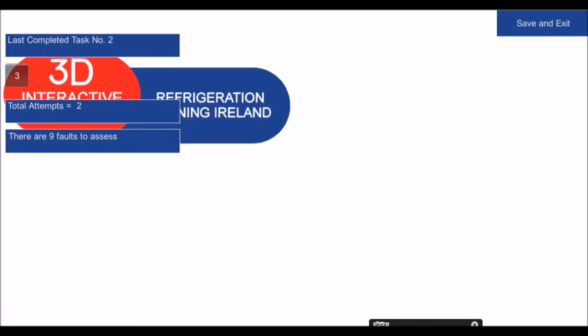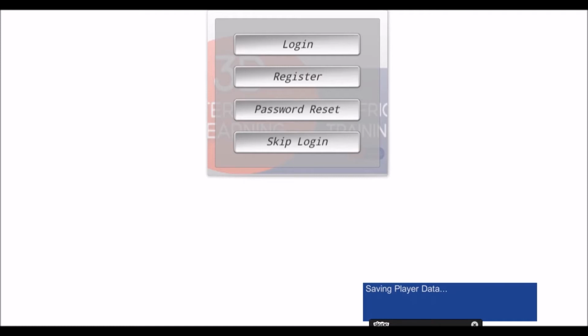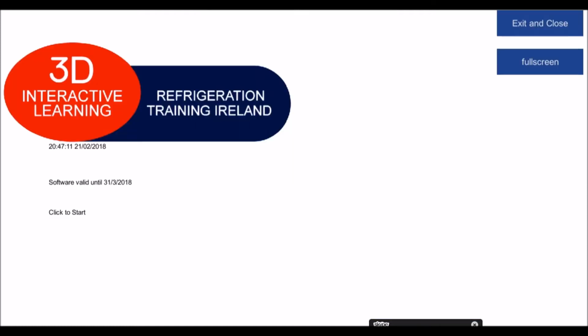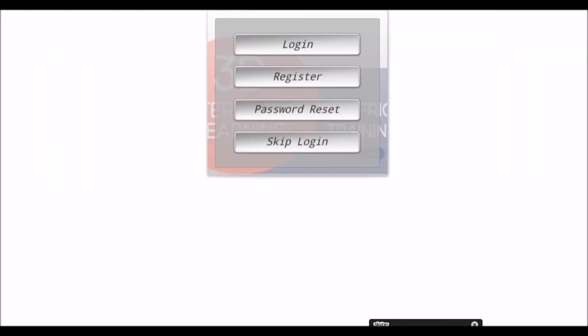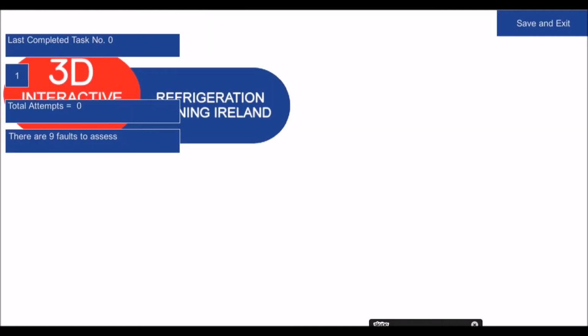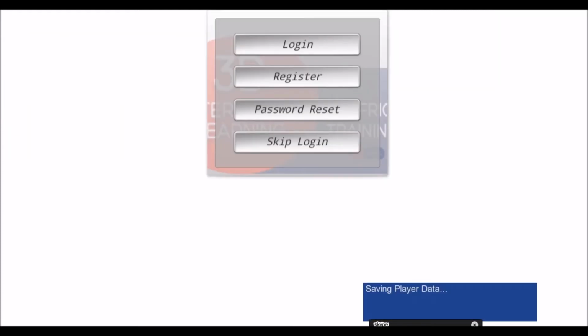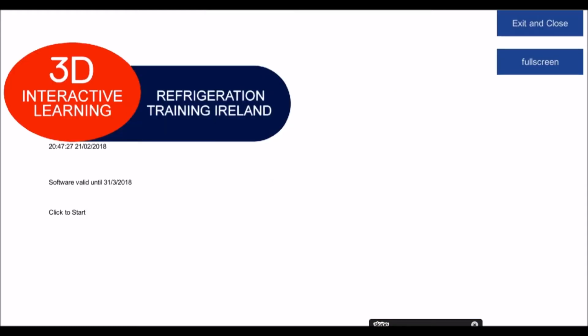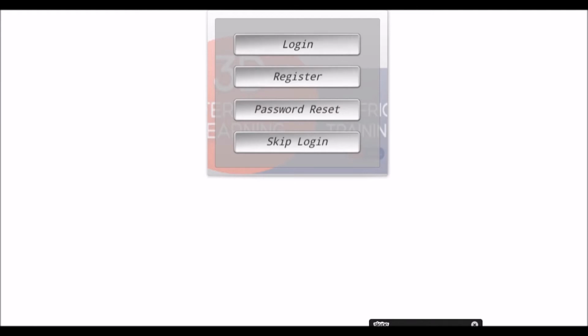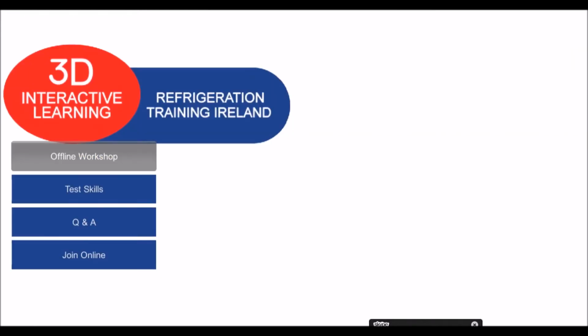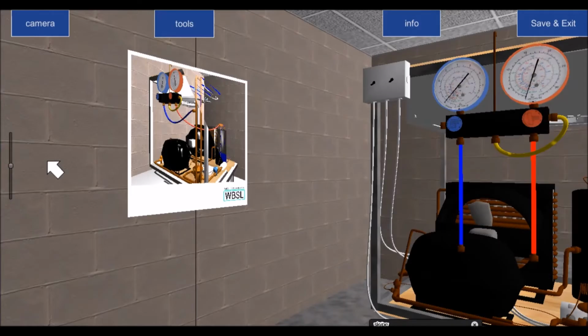Now we must be right, because it's showing me number 3 here. If I got that wrong, it wouldn't show me number 3, it would stay on number 2, and it wouldn't allow me to go on any further. So you can do the rest yourself, as there are 9 faults there and we've only done 2 of them. I'm trying to get you to use the thermometer as a first resort and not to go near the gauge manifolds themselves. Only use the gauge manifolds as a last resort. The manifold would only go on for you to be able to carry out whatever repairs you need, or to confirm the diagnosis that you make.